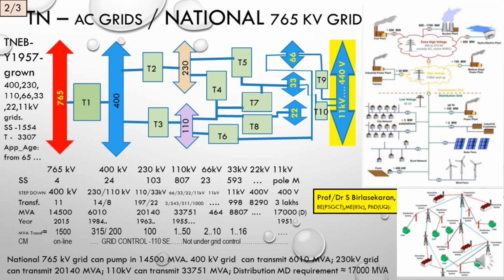Now let us look into the layout. The 765 grid is the national grid installed very recently with 4 substations, and it's reduced to 400 kV with about 11 transformers to transmit about 14,500 MVA, and the year is 2015. The MVA capacity of each of the transformers is 1500 MVA, so big, all imported with online condition monitoring technique to identify any coming faults. And it's connected to the 400 kV grid and 230 kV grid, which are the smart part of the TNEB grid control system managed by 110 superintendent engineers to distribute the load.